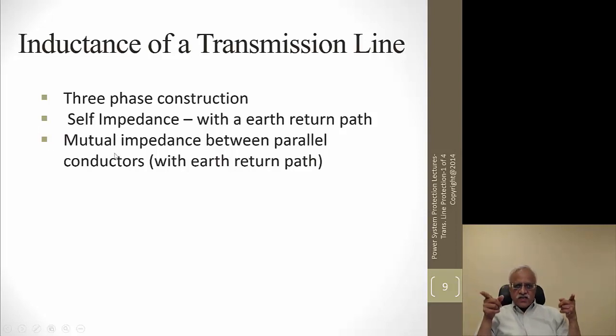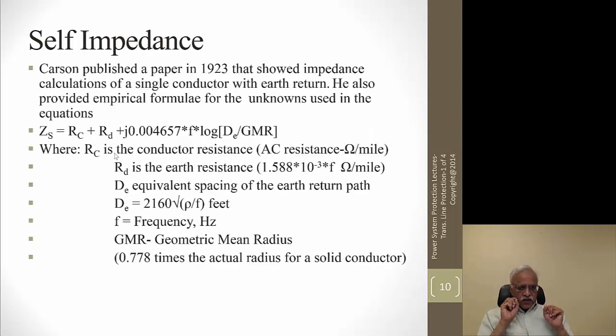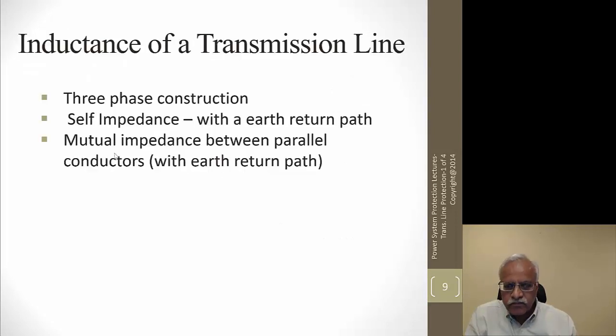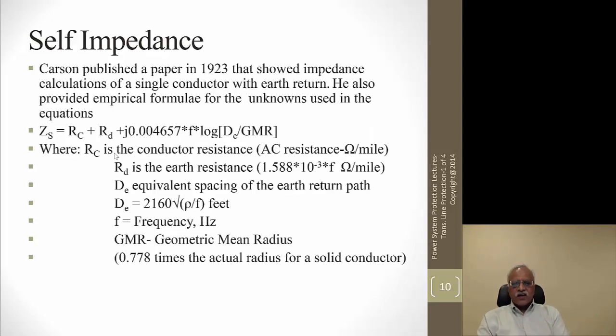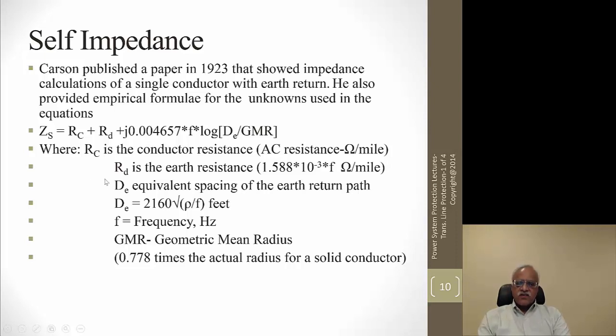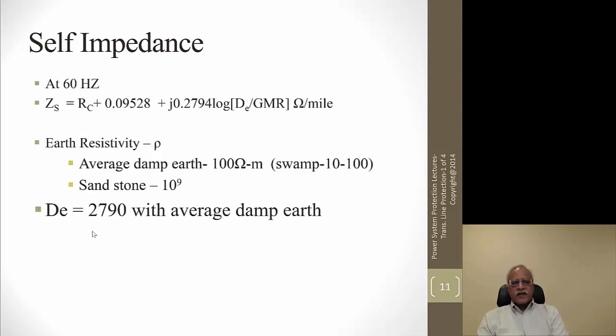The self impedance formula was first developed by Carson, published in a paper in 1923. The self impedance equation involves dE, the average distance between each conductor and the return path. For a single conductor, it is dE divided by the geometric mean radius. Depending on soil type, earth resistivity varies — approximately 100 ohm-meters for normal soil, 10 to 100 for swamp. For average earth, dE is approximately 2790. These values are available from manufacturers or reference books for various soil types.